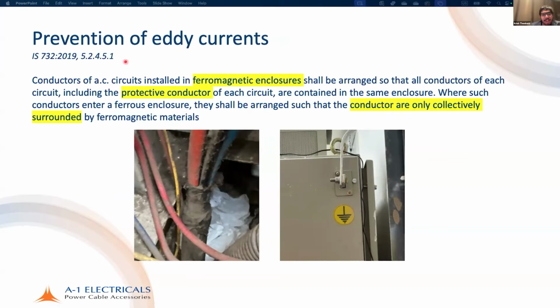Furthermore, when you enter a cable from the bottom and a GI strip from the side, you're violating a requirement in the standard which says that conductors of AC circuits installed in ferromagnetic enclosures shall be arranged so that all conductors of each circuit, including the protective conductor of each circuit, are contained in the same enclosure. Where such conductors enter a ferrous enclosure, they shall be arranged such that conductors are only collectively surrounded by ferromagnetic materials. So they have to enter together. Whereas here, this is from the bottom, this is from the side, you have a bunch of ferrous material between. And this causes eddy currents and heating, which is not a good thing. That's why the standard is requiring that it is arranged in this manner. This is very important. So please keep this in mind.